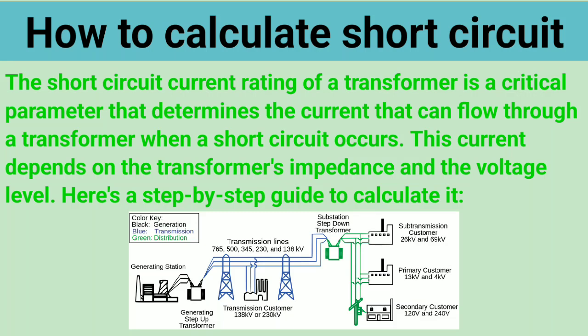The short circuit current rating of a transformer is a critical parameter that determines the current that can flow through a transformer when a short circuit occurs. This current depends on the transformer's impedance and the voltage level. Here is a step-by-step guide to calculate it.